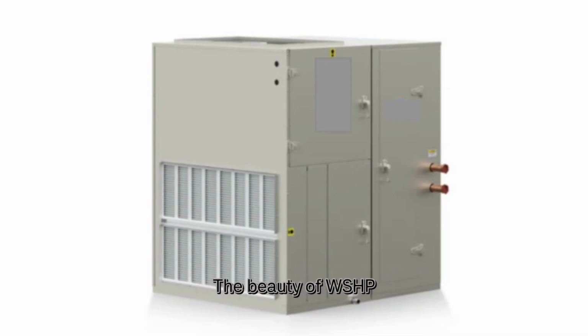The beauty of WSHP systems is their simultaneous heating and cooling capability. While one part of the building may require cooling, another may need heating, and both can happen at the same time using the same loop. This internal heat recovery makes the system extremely energy efficient.